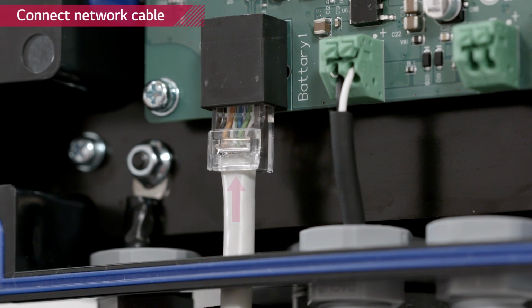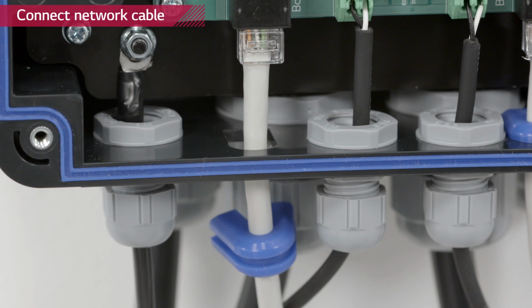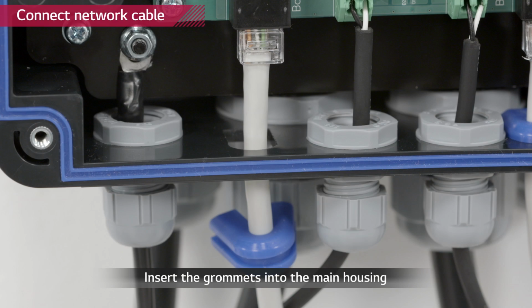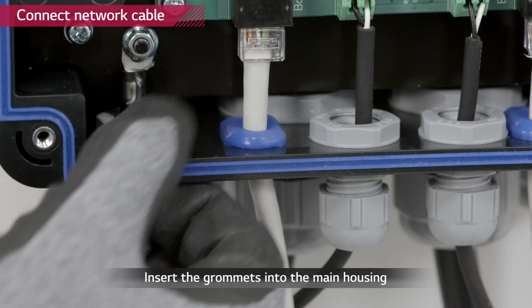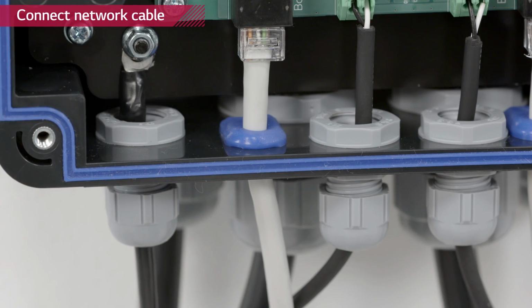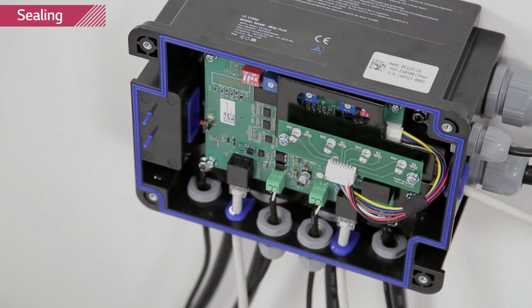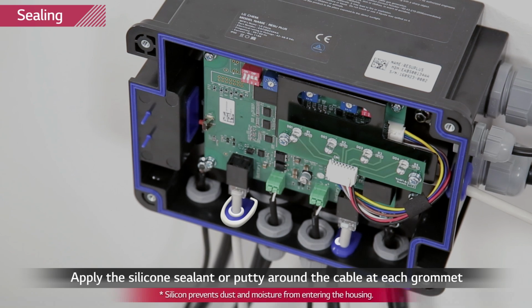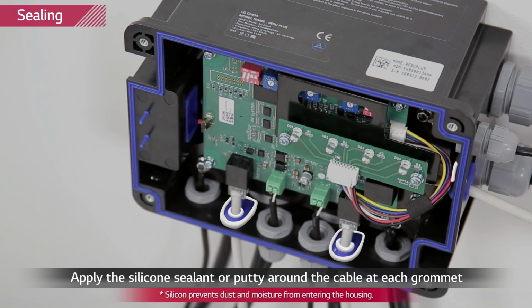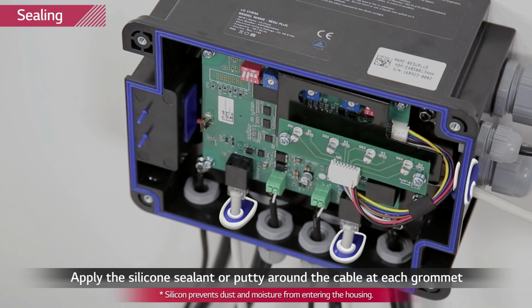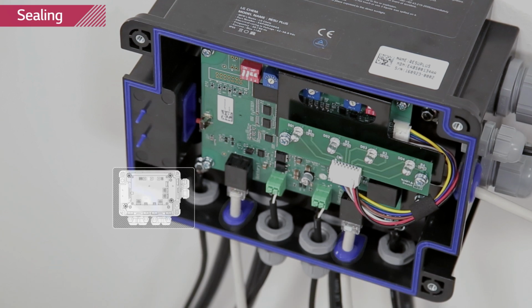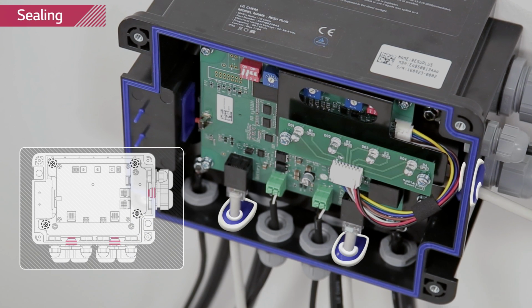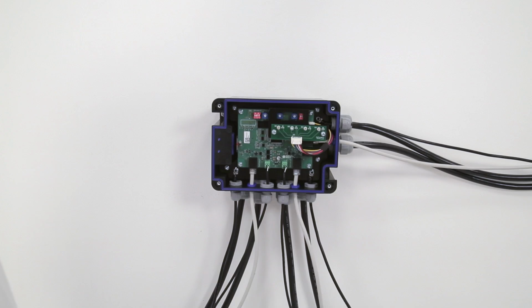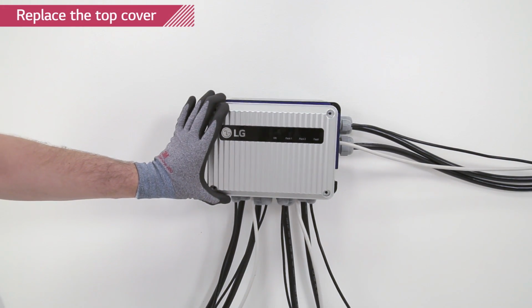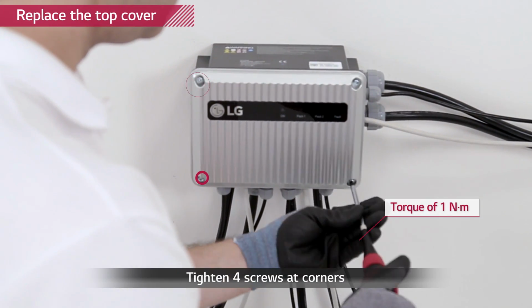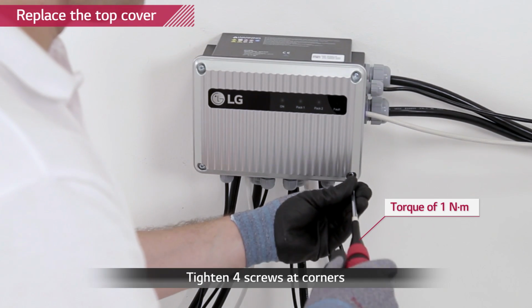Remove the blue grommets. Thread communication cables through the hole and connect to the bank BMS. Insert the grommets to the housing again. Apply insulating material, such as silicone sealant, around the inside of the housing. Make sure that there is no gap, so that the grommet and the communication cables are perfectly sealed. Reattach the top cover and tighten the screws with a torque of 1 Newton meter.